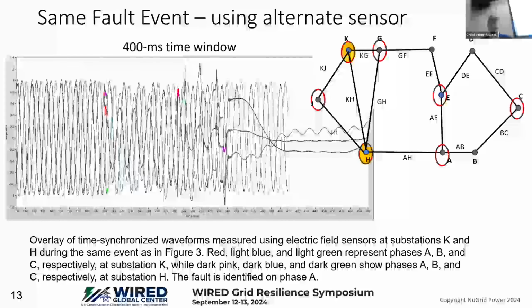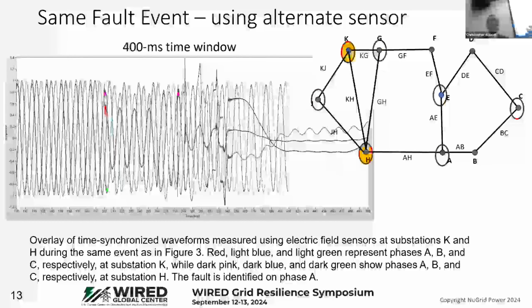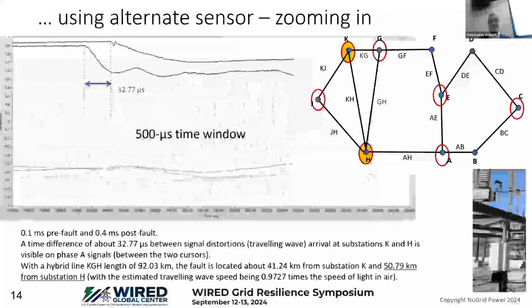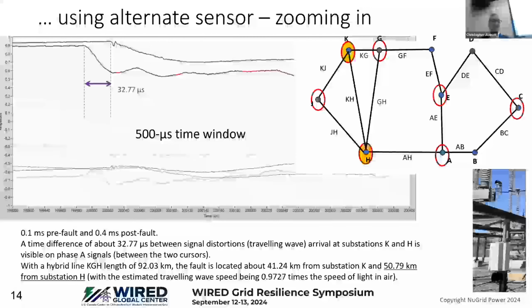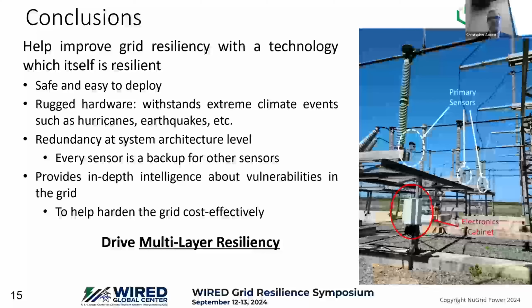But imagine the sensor at substation G is not available. Same fault—you see the waveform at substation H and K, and you look at line KGH as a hybrid line. Again, same analysis, same zooming, of course different time difference, and it locates the fault pretty much in the same location. So it's resiliency of the monitoring system at the architecture level, as well as the hardware has to be hard and good.